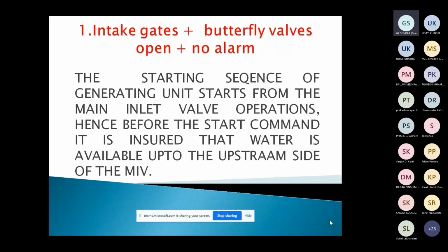Even if they are opening it, but your signal may not be coming, that means the limit switch may be broken, or the wire connected between the limit switch and your control may be broken. You have to say it. Correct, then on to the next one.